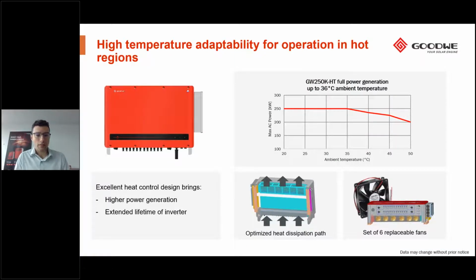Hot areas have been popular in the past, and the popularity is increasing. For that, it's critical to have components that are adaptable for operation in hot regions. Heat control and heat dissipation are critical to ensure the cooling of the components inside the inverters. We provide a set of six replaceable powerful fans with the inverter, allowing it to produce at full power up to 36 degrees, only starting to derate after that, and still being able to generate at a very high level of 90% even at 45 degrees. This increases not only the power generation, but also extends the lifetime of the inverter.